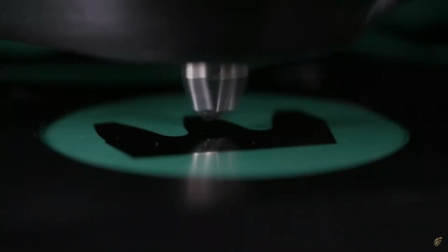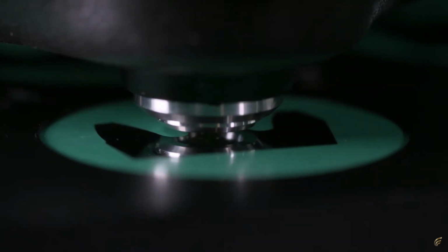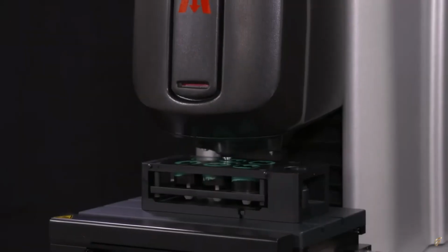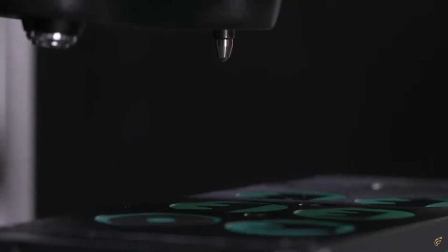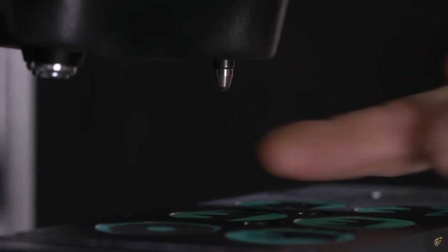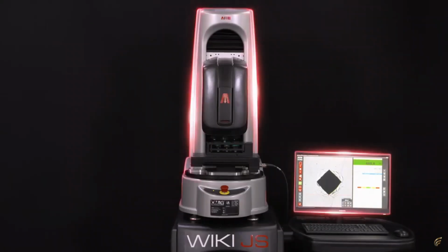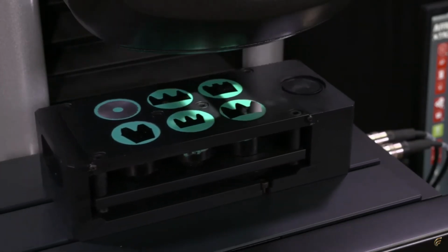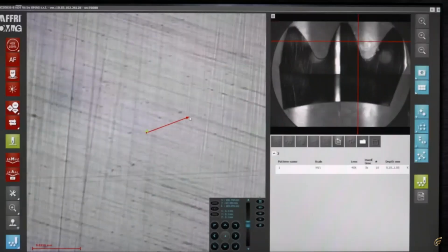It has a rotating motorized turret angled at 7 degrees for the automatic selection of indenters, lenses and laser pointer. It boasts a full body anti-collision safety system. It has a motorized table on two axes with an accuracy of 0.5 micron steps for positioning the pieces.